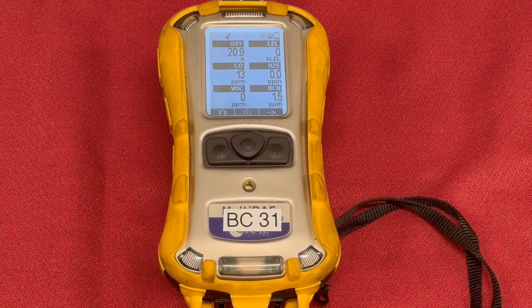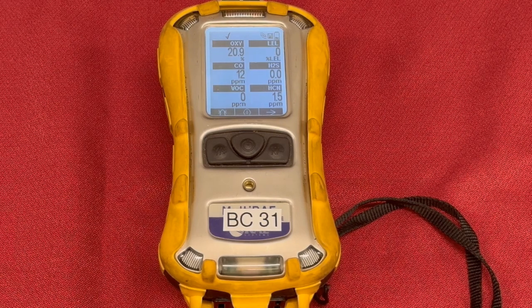That has a 90% safety factor built into the meter because a lot of combustible gases are a lot more volatile than natural gas. So that safety factor, if you're going up against propane or butadiene or something that has a much higher volatility, gives you that safety margin to be able to exit the building. Obviously, this is a sensor where we're not going to put on an air pack necessarily, but we're going to get out of the structure, ventilate, and figure out what's causing the leak.